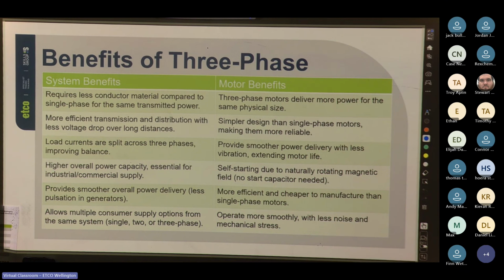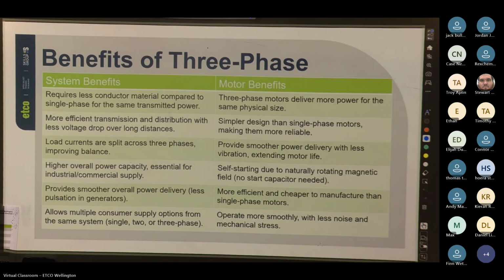On the motor side, a three-phase motor produces more power for the same or smaller size. The design is simpler and more reliable. There are fewer components that can fail. And they also run much more smoothly with less vibration and mechanical stress, which helps them last longer. When you guys come to do your block course, you will be hooking up motors, including single phase and three phase, and you'll hear that the single phase motors sound a lot more angry when we turn them on. Cool. So less mechanical stress, which helps last longer, and they can also be made to be much more powerful. So self-starting. So, where's my mouse? Cool. So most three-phase motors are self-starting, which means we don't have to use external devices.